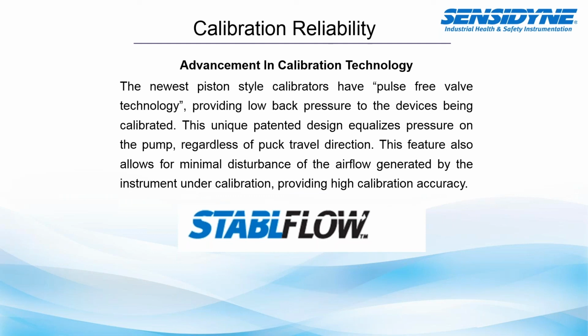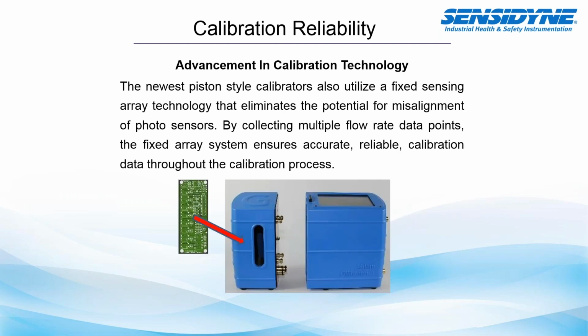Again, the newest piston-style calibrators have pulse-free valve technology, providing low back pressure to devices being calibrated. This is a unique and patented design feature which equalizes the pressure on the pump regardless of the puck travel direction. This feature also allows for minimal disturbance of the airflow generated by the instrument under calibration, providing the highest level of calibration accuracy. So having a stable piston moving up and down that doesn't slam up and down doesn't create that bias artifact. Therefore, a constant flow pump will not see a change in pressure and then react, creating that yawing effect.